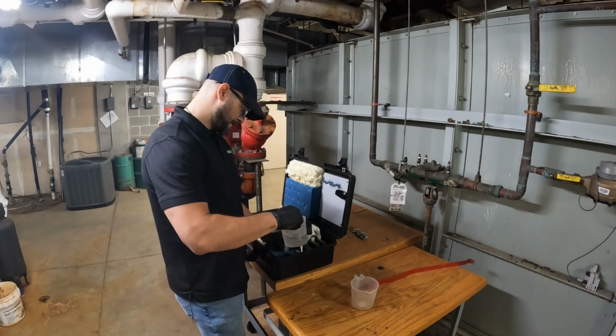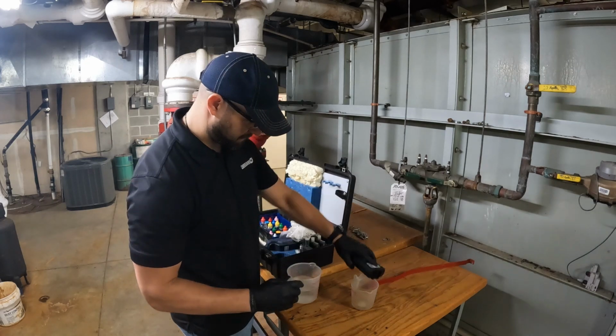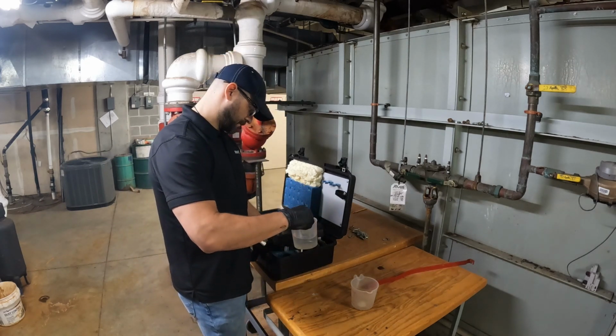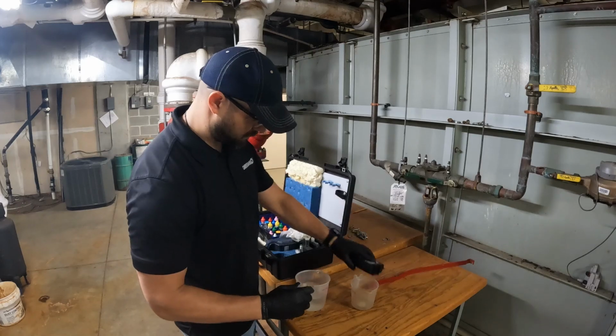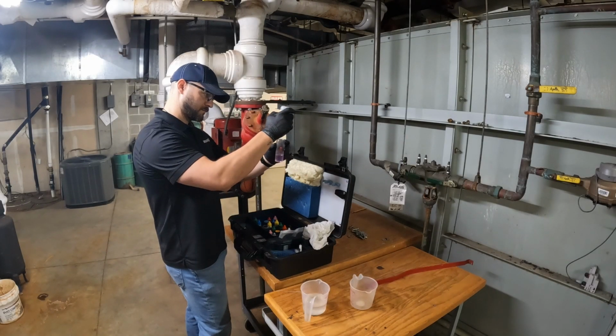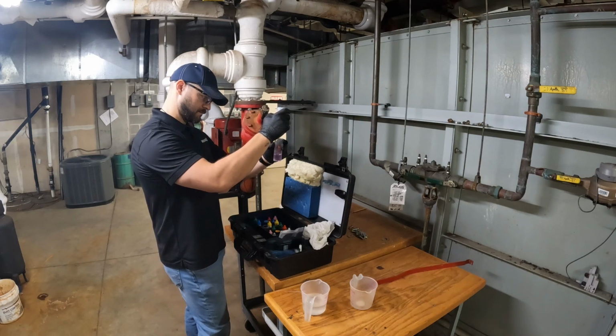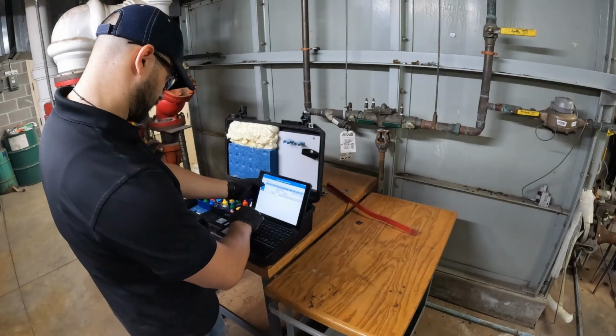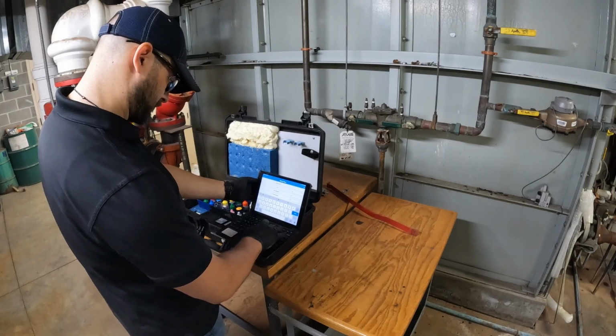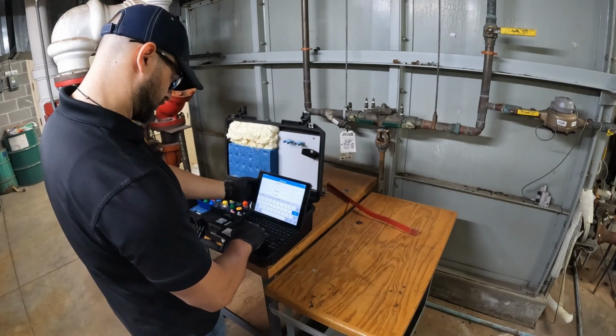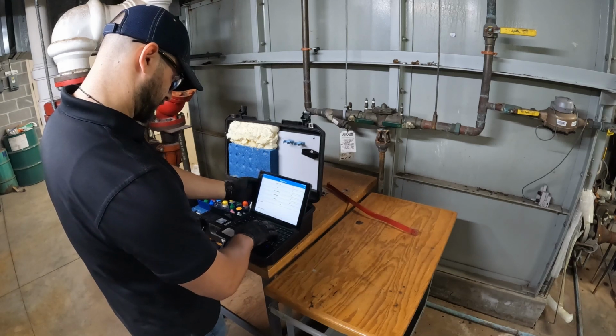Always do your testing on site for the makeup water and system water so you can make any needed adjustments before leaving. Remember to always triple rinse before each test to eliminate any contaminants in your testing. Record all of your results in SmartFSR and put any notes and system photos. It's also a good idea to take a picture of the controller for a timestamp to verify that you were there. Be sure that the date and time are correct on the controller when taking the timestamp picture.